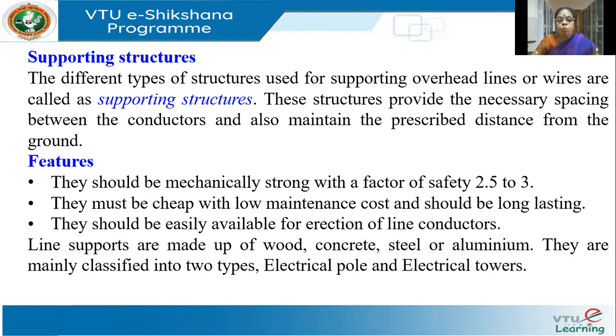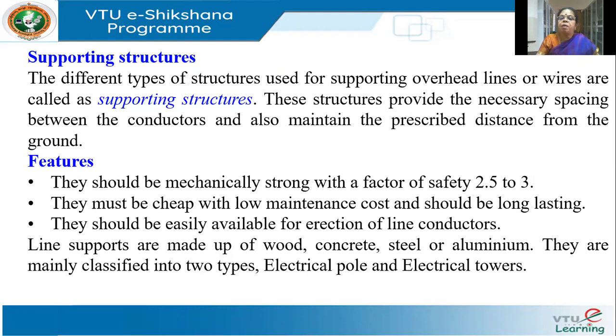The supporting structures should be mechanically very strong, because if the support fails, the conductor itself will fail. Normally, a factor of safety of 2.5 to 3 is used. Factor of safety means your design value gives you some value x, and you take two or three times that so it will be safe. It is like having a reserve — when you go out shopping and want to buy something for 1000 rupees, you carry extra, because prices may have gone up.